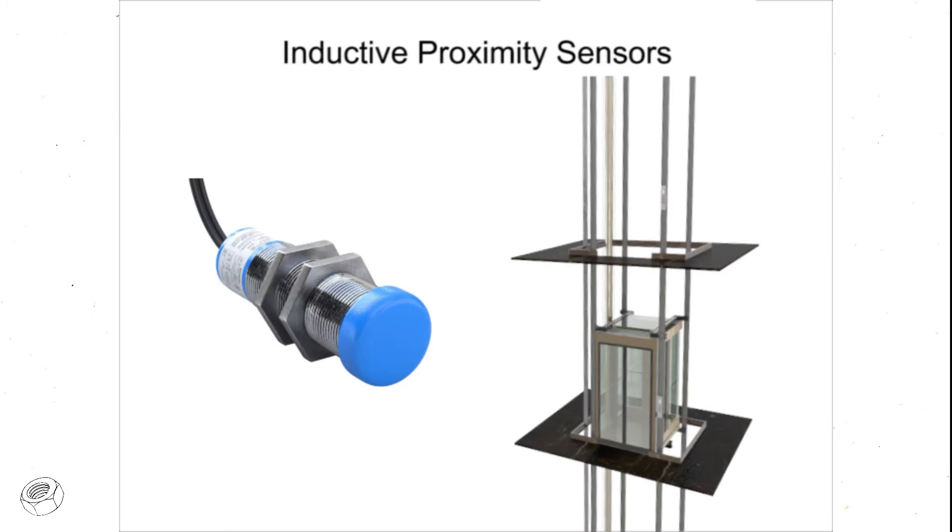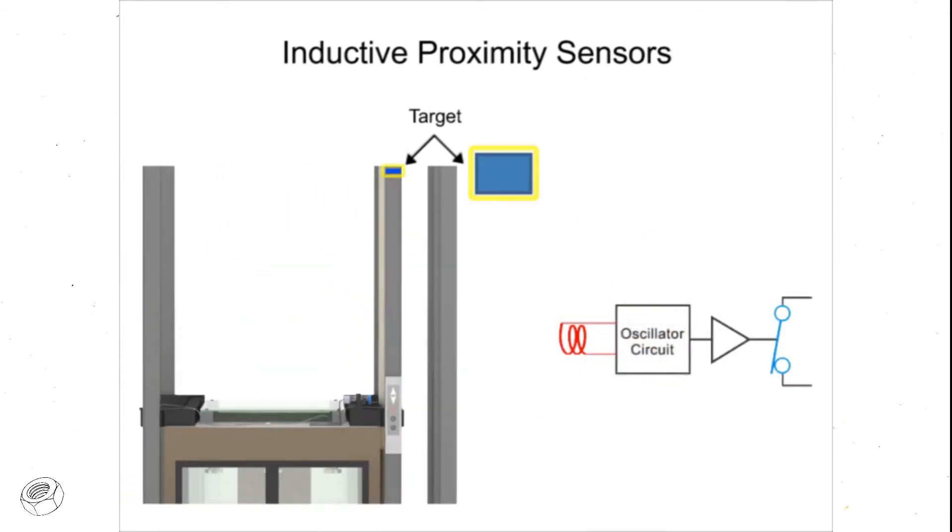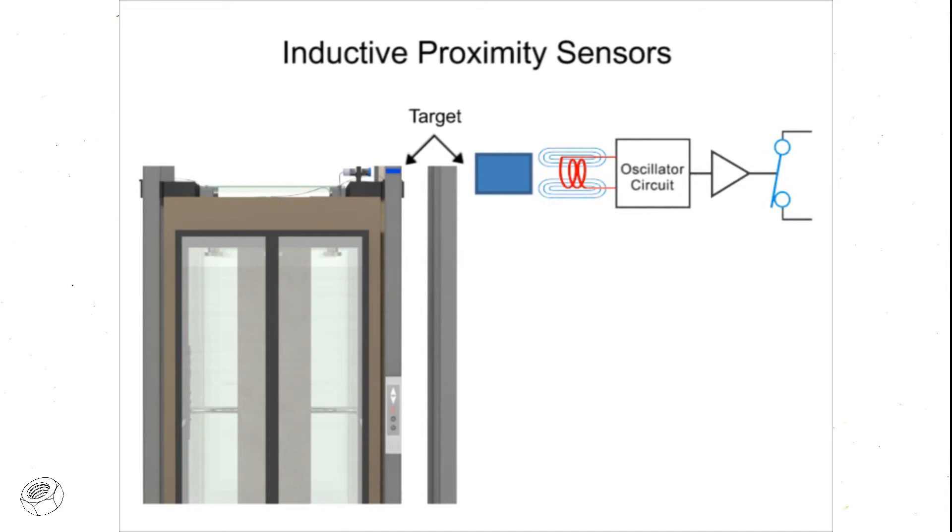Inductive sensors can detect a target from 0.5 millimeters to 40 millimeters. They only detect metallic targets and therefore use a magnetic field to detect its presence. When a ferrous metal material enters the magnetic field, electrical currents known as eddy currents are induced on the metal surface.